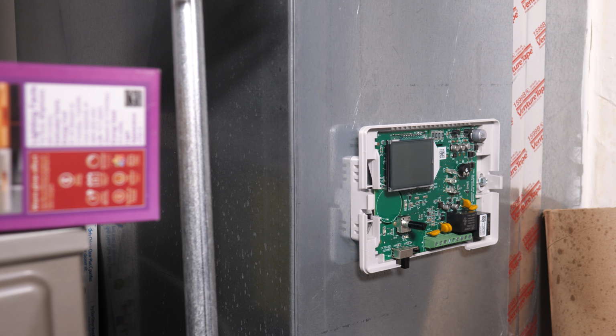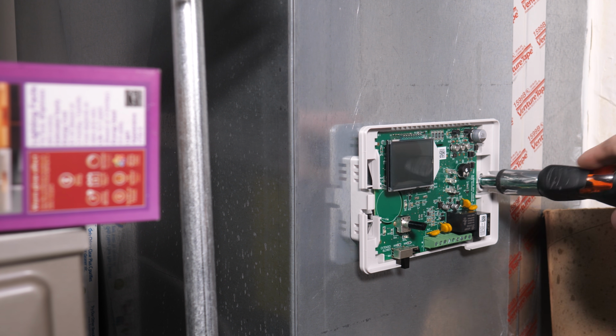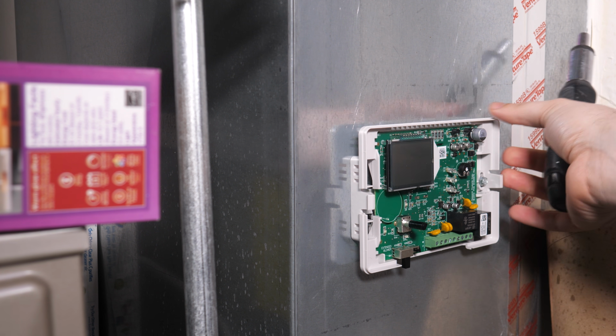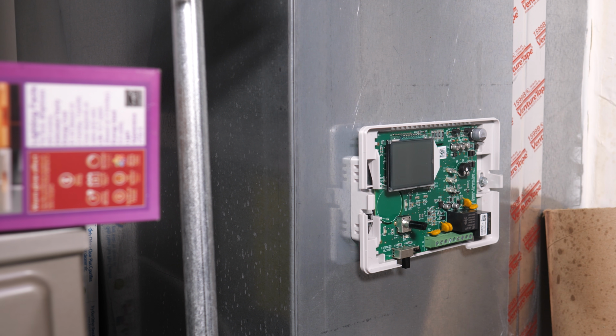My home's setup means that whenever the furnace blower is running, the humidistat is going to get a pretty accurate reading. But I can think of plenty of cases where it would be better for the humidity sensor to be somewhere else. In those cases, you might be better off getting a fancier thermostat which can control a humidifier remotely. But if your home's HVAC system was designed reasonably well, like mine was, taking a reading of the air entering the furnace or air handler should work fine.